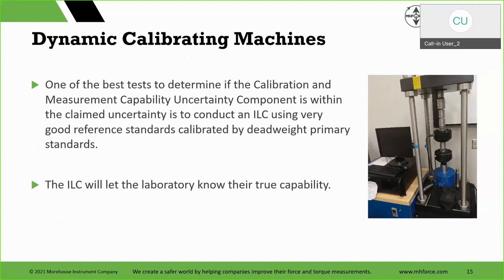The other thing, one of the best tests. If you have these machines, one of the best tests to say how good is this, because we've seen ridiculous claims that are much too low. We've seen people using them with conservative uncertainty statements, and people using them with not so conservative uncertainty statements. The best thing to do, if I'm claiming 0.03 or even 0.05, is to do an ILC with good reference standards. Or I can do my own ILC where I take two of these load cells pictured here and calibrate them with deadweight primary standards, and then compare them against each other. And you know what? The difference that you see between those two calibrated with primary standards is really a representation of your true capability.